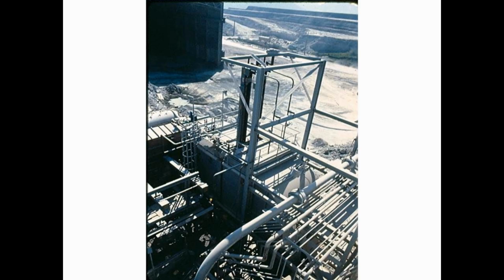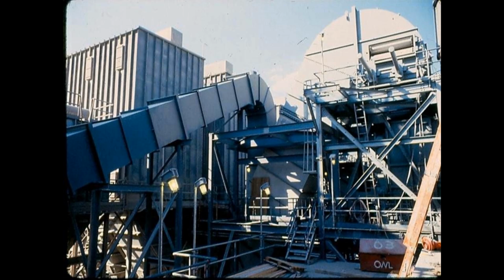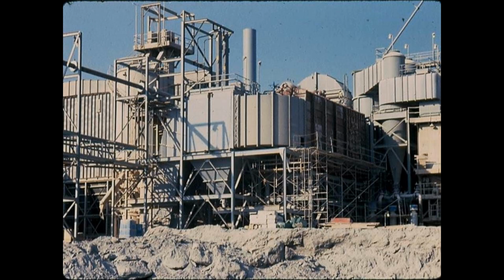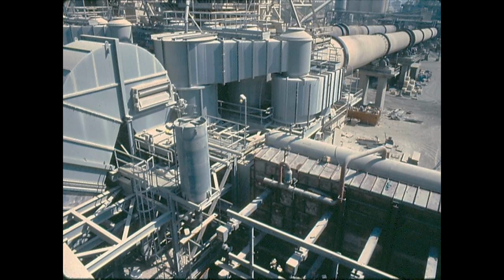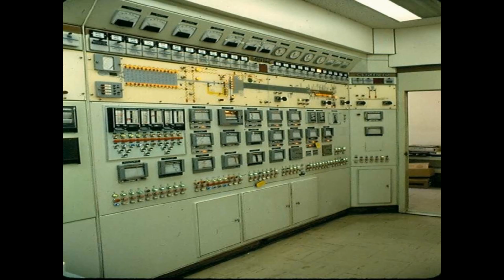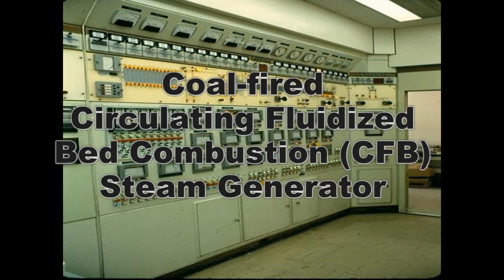As a means to enable the waste heat boiler to be bypassed during shutdown, a cooling air damper was installed in the bypass ductwork. When the waste heat boiler is isolated by shut-off dampers, the kiln induced draft fan horsepower will increase to the previous 1,200 horsepower. This change from approximately 450 horsepower is accommodated by a new variable speed induced draft fan installed on the kiln to allow both modes of operation.